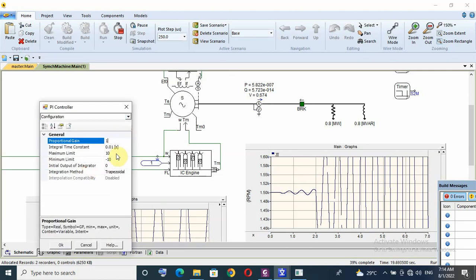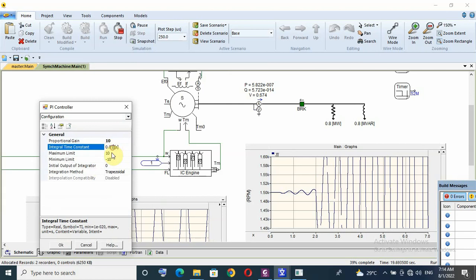So I have to tune because this is very high oscillation. So I have to increase proportional gain from 1 to 10 and I have to increase also integral gain or decrease integral time. So say 0.01, say 0.005.